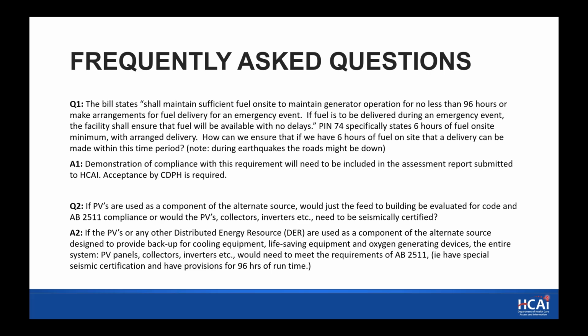Next slide. Question number 2: if PVs are used as a component of the alternate source, would just the feed to the building be evaluated for code and AB 2511 compliance, or would the PVs, collectors, inverters, etc. need to be seismically certified? So if the PVs or any other distributed energy resource are used as a component of the alternate source designed to provide backup power for cooling equipment, life-saving equipment, and oxygen generating devices, the entire system, PV panels, collectors, inverters, etc., would need to meet the requirements of AB 2511. That is to say, they would need to have special seismic certification and provision for the 96 hours of runtime.